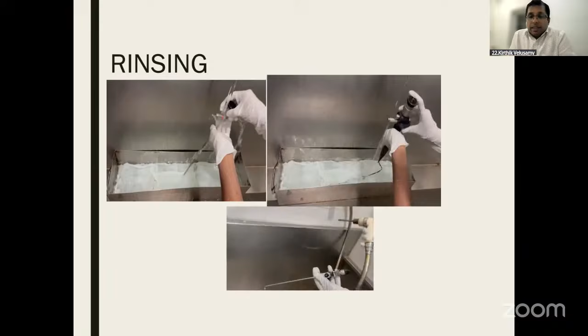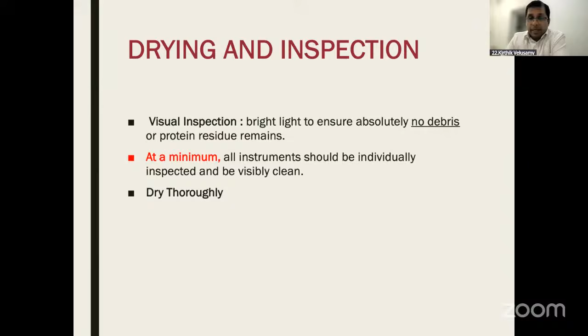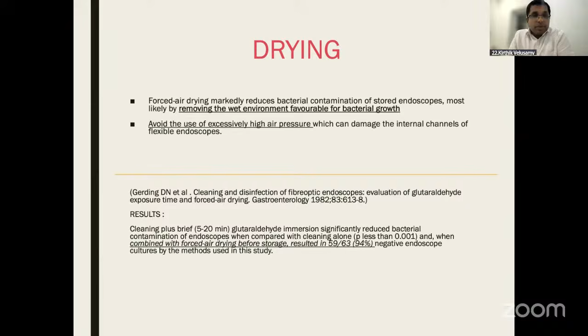Then once we do the rinsing, we need to inspect. At the minimum, all instruments should be individually inspected, and they should be visibly clean. Then this is followed by drying. Drying is very important because otherwise the damp environment allows the bacteria to regrow and form a biofilm. Avoid using high pressure as it can damage internal channels of the flexible endoscopes and also rigid scopes.